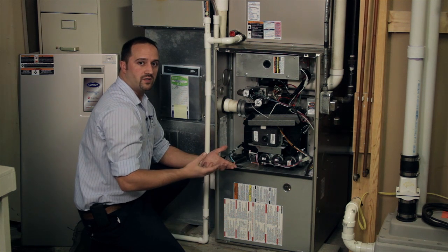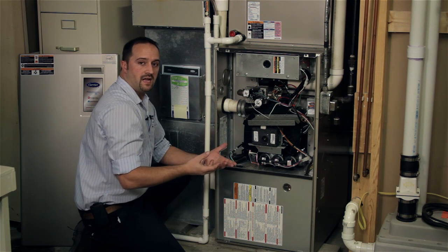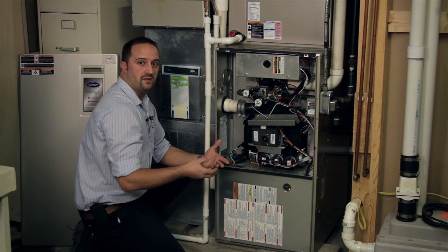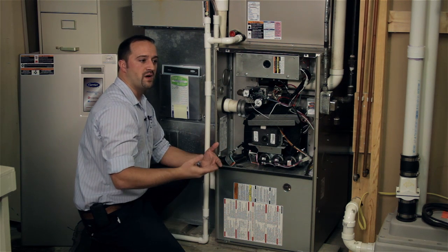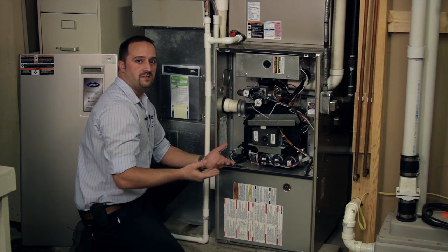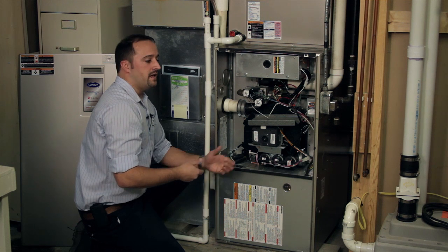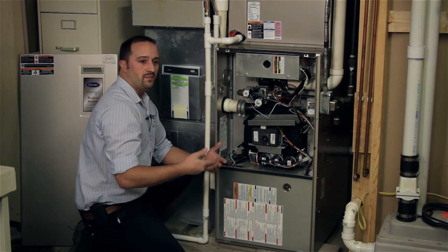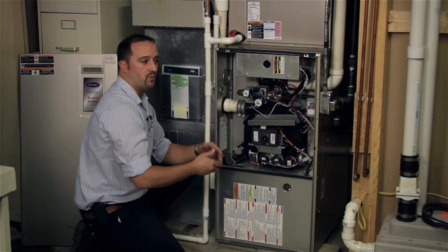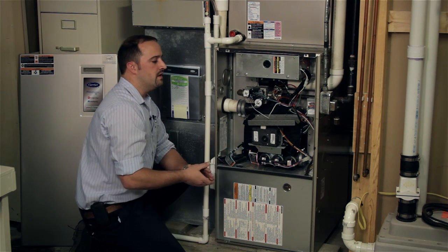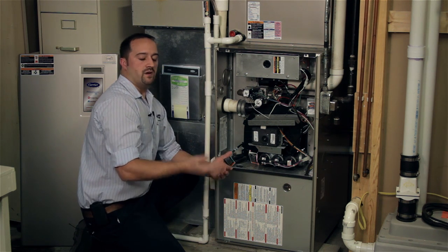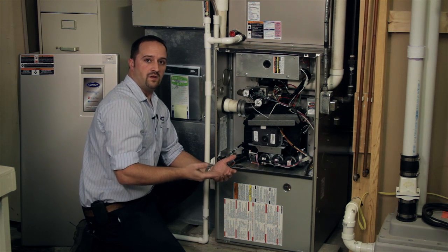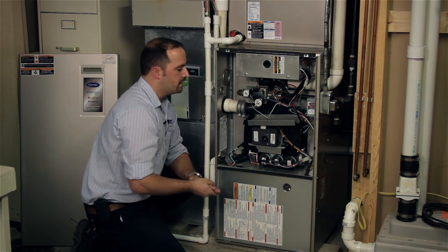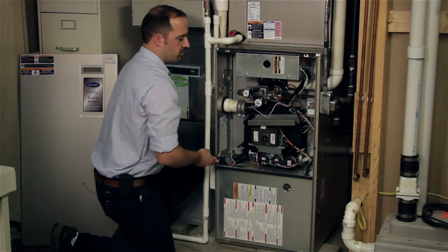How much power a motor consumes is directly related to how efficient it is as well as its life. If it starts pulling more power than what it's rated for, that's basically saying that it's coming towards the end of the life. He can make that recommendation then to you, say, hey, you might want to think about changing this motor out or this whole piece of equipment if it's too old, because we don't want it to break down on you come the middle of winter at 2 o'clock in the morning. So that's one of the things he's going to check for.